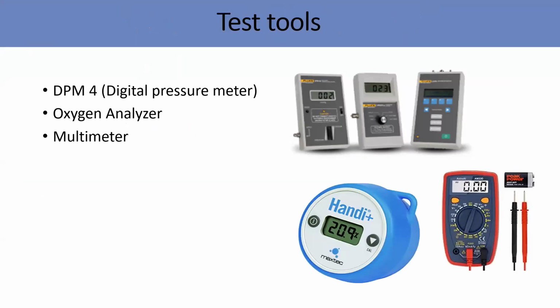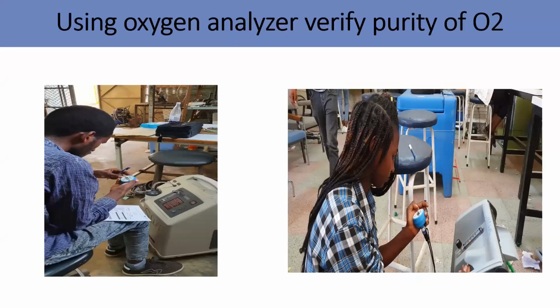Preventive maintenance. This is always an interesting part for BMET. Normally, when you talk about preventive maintenance for an oxygen concentrator, you need to have a digital pressure meter, an oxygen analyzer, and a multimeter. And very important, a screwdriver, because you have to open up the unit. But normally for test tools, we need these three to verify the performance test. So these are the biomed technicians and biomed engineers using them to verify the purity of the oxygen concentrator. This is how they do it with the checklist, verifying the particular unit.